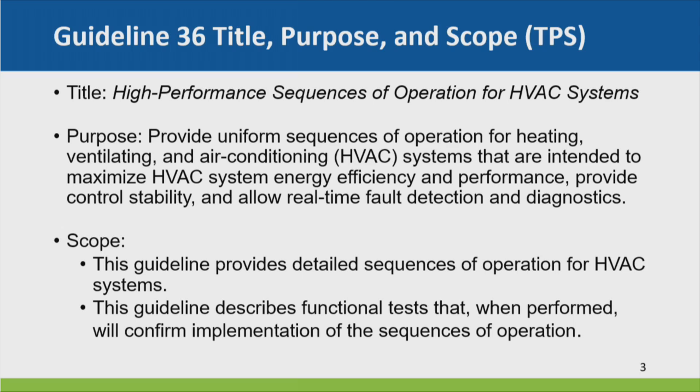So our purpose is to provide uniform sequences of operations for HVAC systems that are intended to maximize system efficiency and performance, provide control stability, and allow for real-time fault detection and diagnostics. And it covers all HVAC systems. The last line says we're also including functional tests in there. We haven't done that yet, but ultimately we're going to be getting into that.